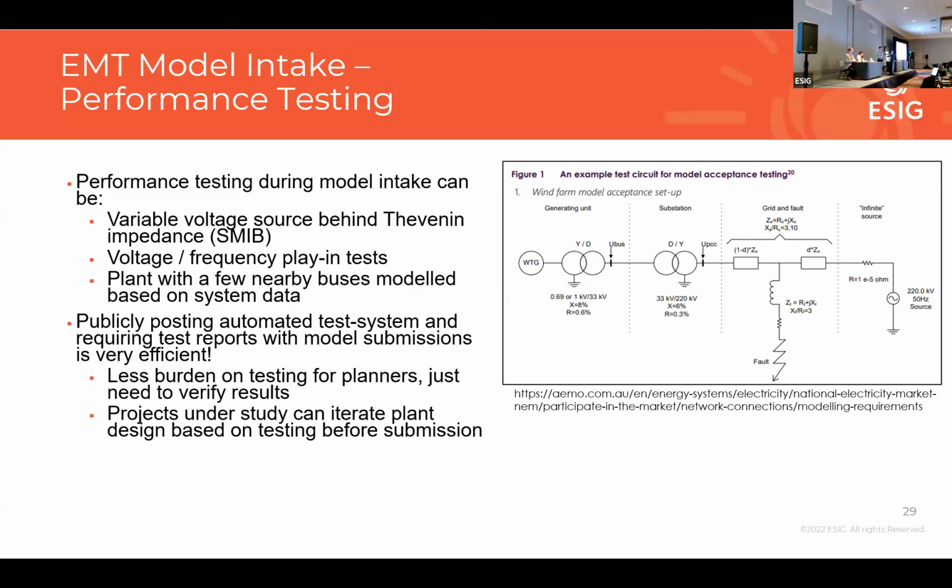So this can look a number of different ways, and I'm hoping we'll see more alignment in what folks are asking for in these test systems as things like IEEE 2800.2 come online, which is going to lay out exactly how folks should be testing plants against the IEEE 2800 performance requirements, which is essentially missing in industry at this point.